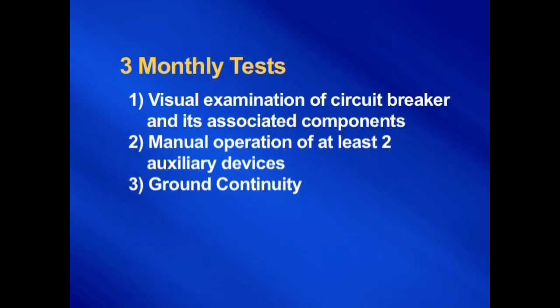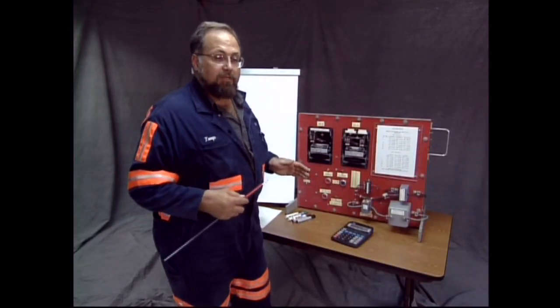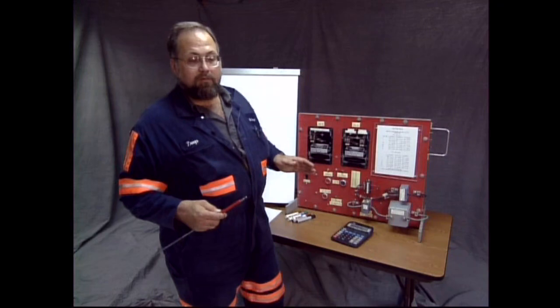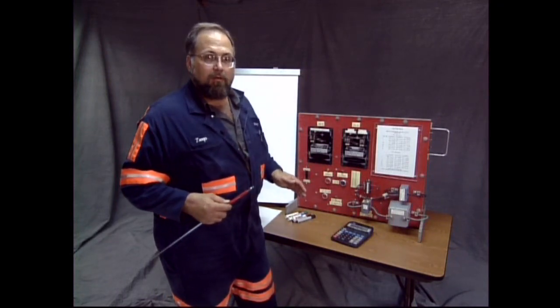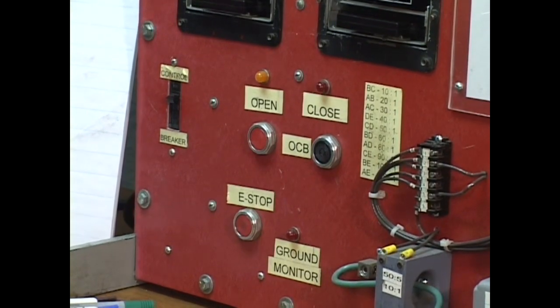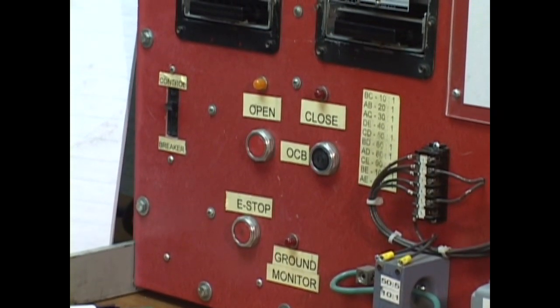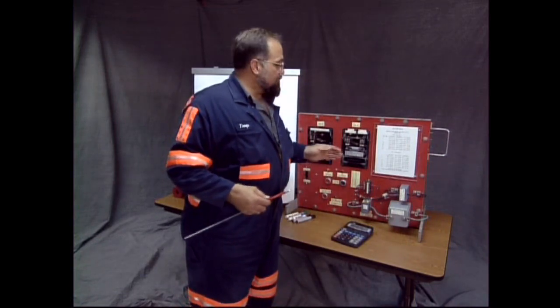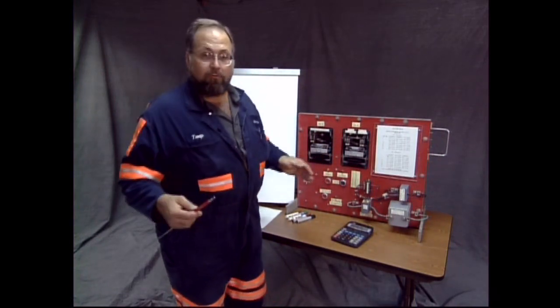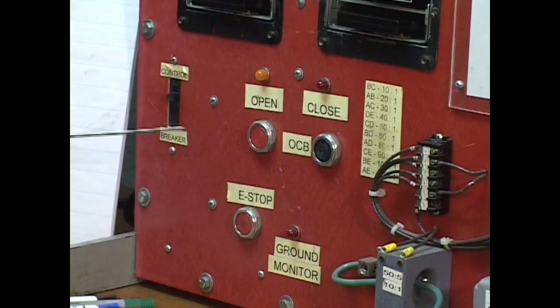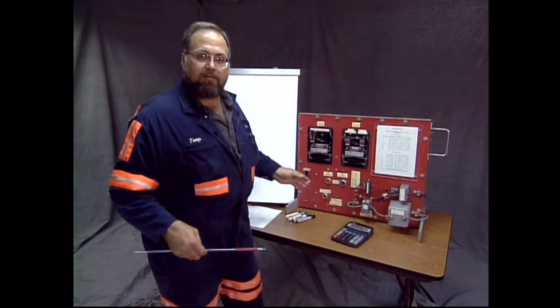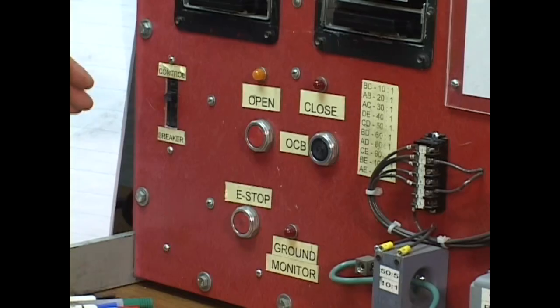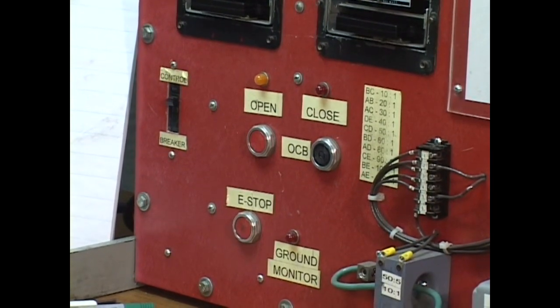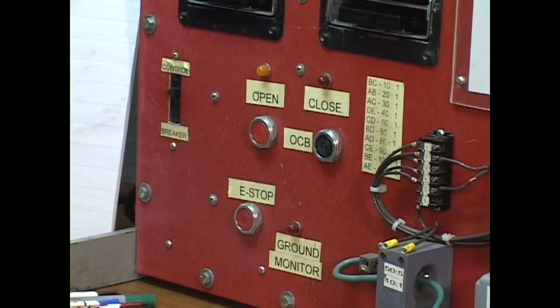Your last test, you can't perform from this location. If you're checking for monthly permissibility, this circuit breaker and its devices, you can't perform the final check from here. You have to go to the furthest point protected by this breaker and operate an e-stop to prove ground continuity to that point. If you break the ground continuity circuit at the furthest point, this breaker should fall. The e-stop is placed here for your convenience in testing. In real life, that's not going to be right beside you. You have to go to that point or have someone stationed at that point to operate that e-stop to prove ground continuity.